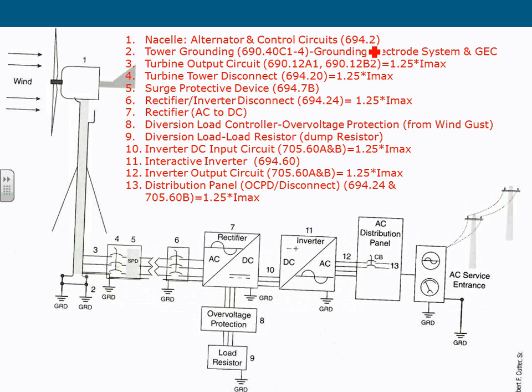So the smarter approach, I always say, number 5, will be the so-called surge protective device. We'll talk about this one, guys. I have a couple of details about it. For those familiar with it, there are 3 types: type 1, type 2, type 3. Type 1, you put on the line side of a disconnect. Type 2 on the load side of the disconnect. And type 3, you put right where the outlet is behind you, in one of these outlets. Type 1 is the most robust, and type 3 is the least robust in terms of handling the surge. So that's my surge protective device. Any comments, any questions about surge protective device?